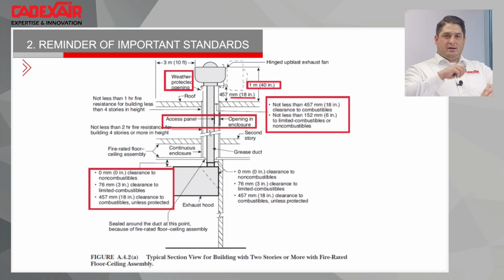So you cannot plug 2 kitchens on the same ductwork if they are on 2 different stories. So you will need to have different ducts going outdoors. I will say the main idea is that as soon as you go outside of a fire zone with almost any other thing, they will have a means to stop the fire. So if you have a normal HVAC ductwork, they will use a fire damper. But in NFPA 96, you're not allowed to use any fire damper.